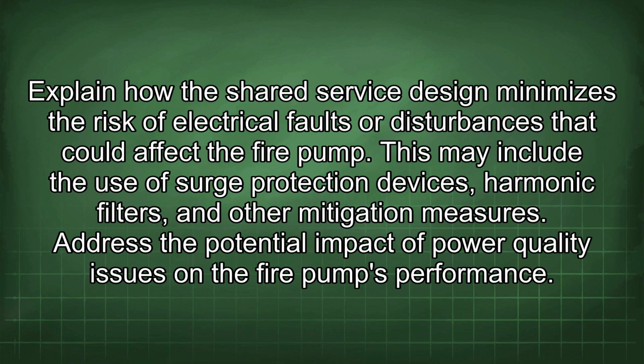Explain how the shared service design minimizes the risk of electrical faults or disturbances that could affect the fire pump. This may include the use of surge protection devices, harmonic filters, and other mitigation measures.